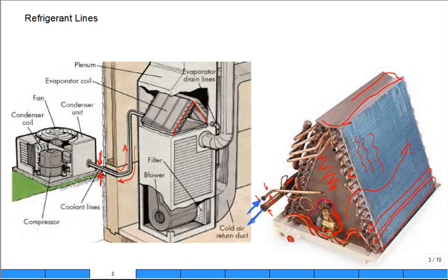It's sealed right in here, so airflow can't go there. It's forced to come and do a Z-shape across the coil and come up. It's sealed up here, so the air has to go through the coil. Now, once they have two feeds on this side, they come up here, you can see one, two coming out. And on the other side, there's two coming out. And they collect in a larger suction line, manifold. There's a little Z to it. It goes back, and then it comes out this way. There. So, there you go. There's the flow of refrigerant through that evaporator. It's called A-coil because of its shape, and they're very common. The tray collects the water, and there's little hookups to get the drain.